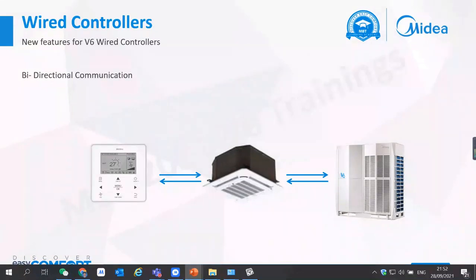So this signal is sent directly to the indoor unit. So now the indoor unit will display 21 degree, but our communication is one-way communication. So the wired controller is still showing 26 degree temperature, because it had sent 26 degree, there is no bidirectional communication. He does not know that the temperature of the indoor unit has now been updated. So this is to differentiate the unidirectional and bidirectional. This is very basic advantage that we have from this.